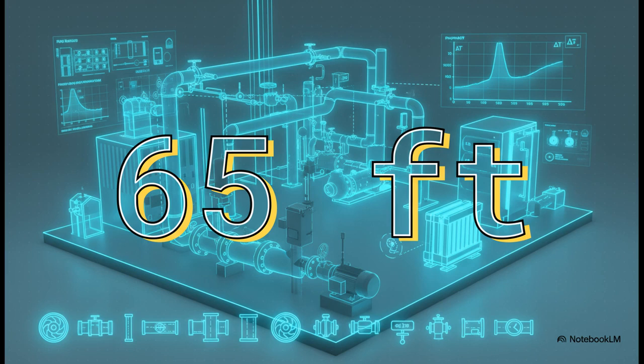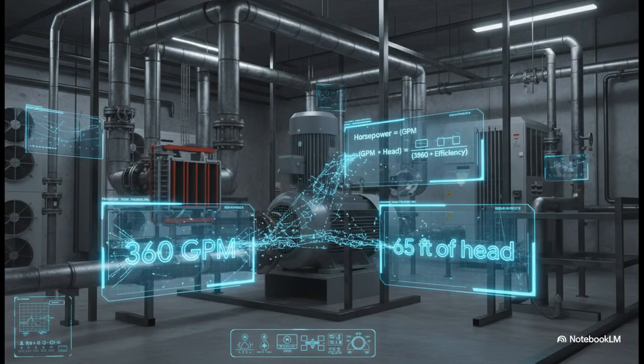That is our magic number. That's our total dynamic head. It is the one single target our pump has to be able to hit to do its job right. Okay, we're on the home stretch. Let's say this particular system needs a flow rate of 360 GPM to keep everyone cool. We've got our flow, we've got our head. Time to plug them into that horsepower formula and see what we get.